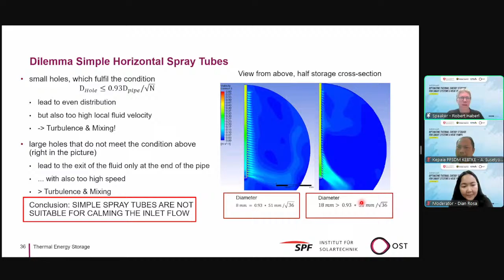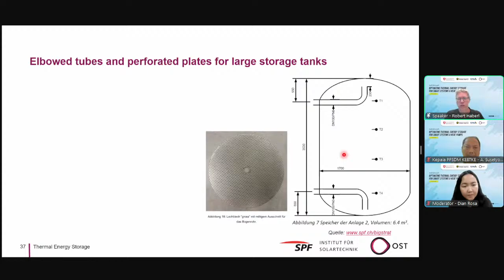The next method to bring water in or out of a tank is elbowed tubes and perforated plates in a storage tank. That is used mostly for industrial cases, where you have only one thermal zone and not several thermal zones. The elbowed tubes guide the fluid into the cover or bottom of the curvature, meaning if you have charging with hot water, it's going up here. And if you use a cold storage, you charge it with cold water, it's going in here to the bottom. It acts as a flow distributor, often used in combination with perforated sheets, meaning a sheet would be placed here in the storage tank and up here with a small hole for the elbowed tube. And the combination very effectively results in a very good stratification.